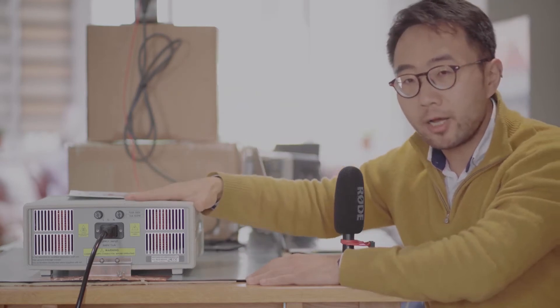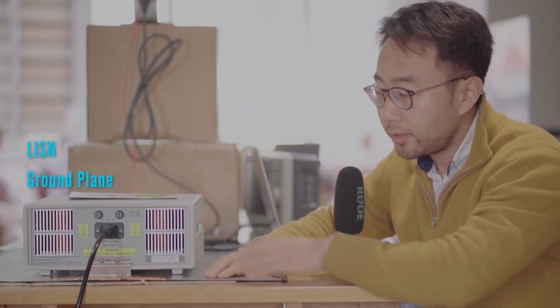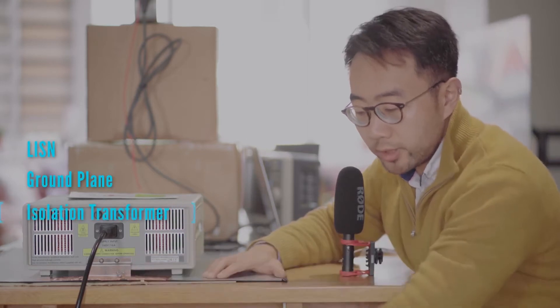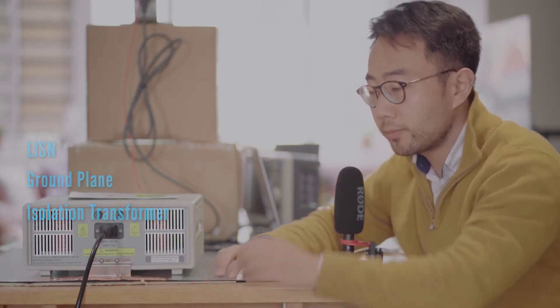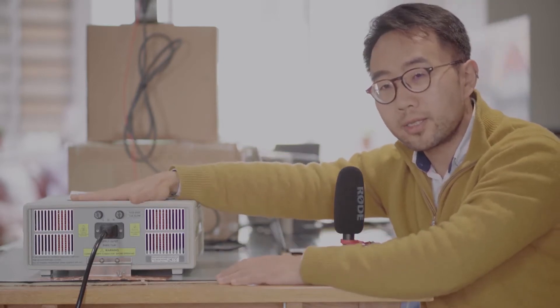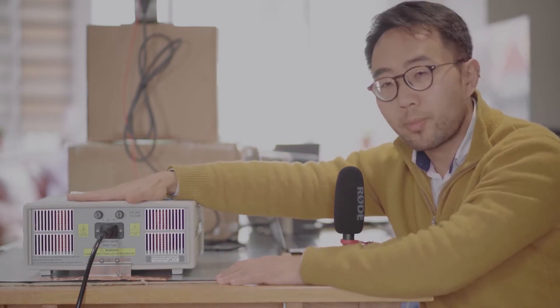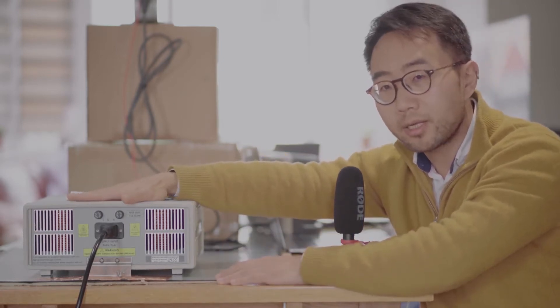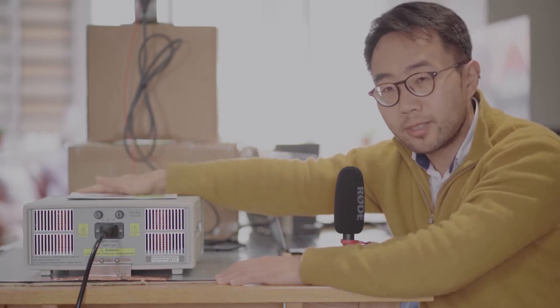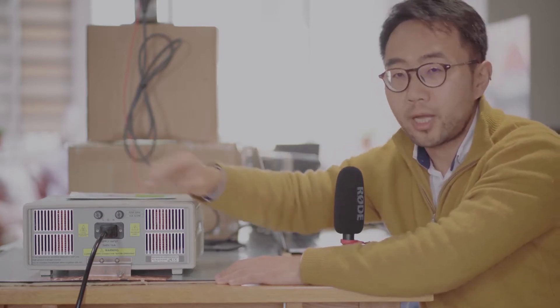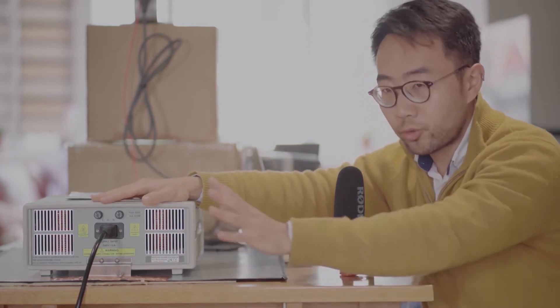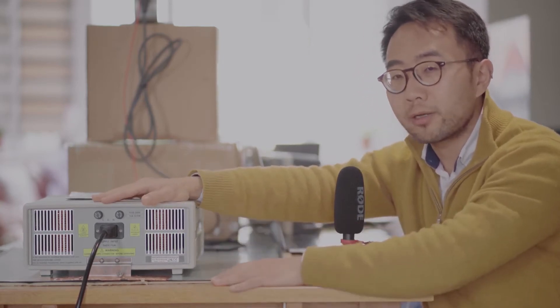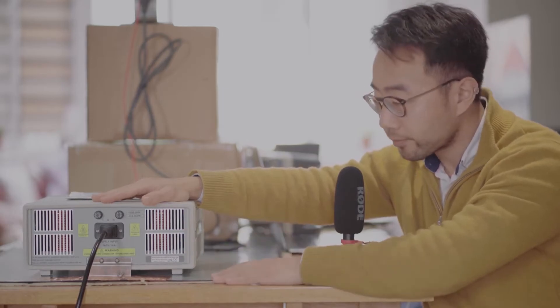Basically you would need a mains LISN, ground plane, and an isolation transformer. The reason you need an isolation transformer is because of the way the LISN is built. They have huge capacity inside. When you switch on the LISN, chances are you will trip the RCD in-house. So you do need an isolation transformer to prevent the tripping from happening.